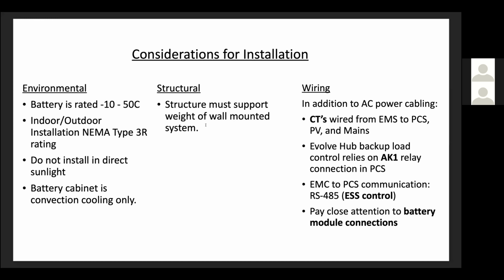Structural considerations: the structure that you're mounting it to must support the weight of a wall-mounted system, because this is a wall-mounted system only. There is no floor mount option for this product as of yet. As far as wiring considerations, in addition to the AC power cabling, those power conductors, there are CTs that need to be wired from the EMS to the PCS to measure the battery, the PV inside the backup load subpanel, as well as any other PV that's behind the meter, as well as a CT run out to the main service panel.